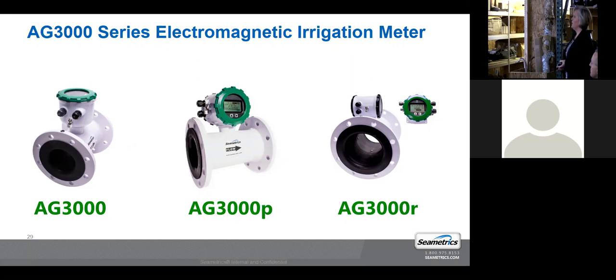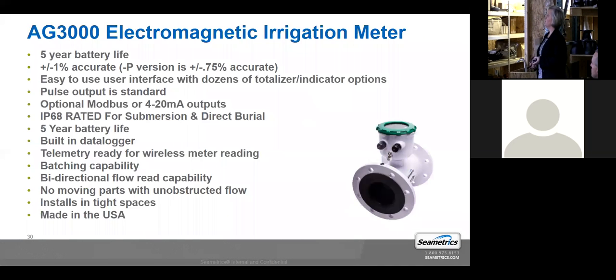It is available in a P premium version, which drops the accuracy down to 0.75%. I think on the P version, you can then get Modbus on the regular version, right? Yeah, on the regular version, okay. The P and the R version, those aren't going to be as common in ag. We more took our industrial municipal meter and made it available in case people wanted more options. The R version is a good one to know about. It's a remote mount register if anybody has the need for a remote read meter.